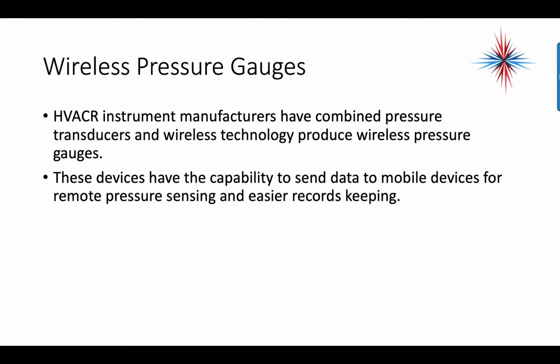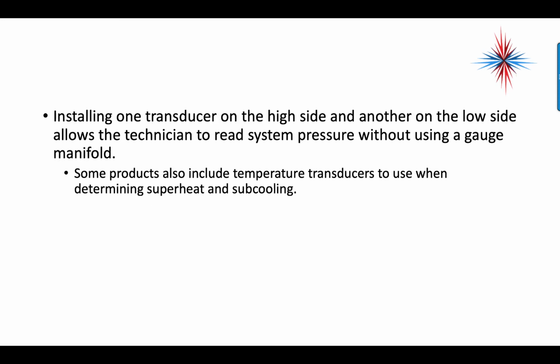HVAC instrument manufacturers have combined pressure transducers and wireless technology to produce wireless gauges. These devices have the capability to send data to mobile devices for remote pressure sensing and easier record keeping. Installing one transducer on the high side and another on the low side allows the technician to read system pressure without using a gauge manifold. Some products also include temperature transducers to use when determining superheat and subcooling. An example of this is the Testo smart probes.